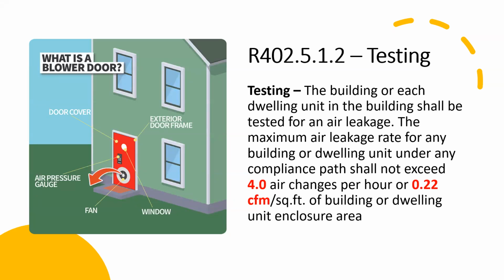For blower door testing, it now drops the ACH to 4 as opposed to 5 ACH. There are allowances for smaller buildings, dropping from 0.30 to 0.22. Basically, it's cubic feet per minute per square foot of the building envelope. So it's a different way of not doing the calculations for ACH, but a different way of reaching the same goal, for smaller buildings. Anything less than 1,500 square feet can use this allowance to get to that number.